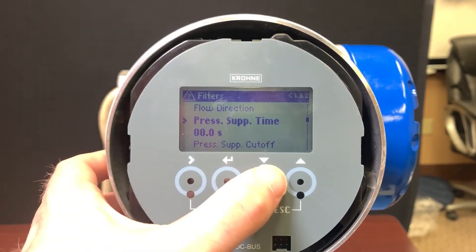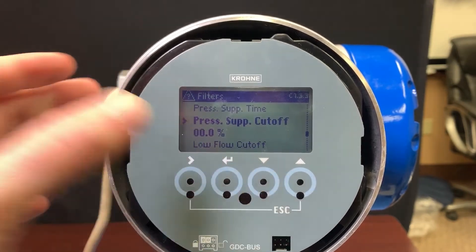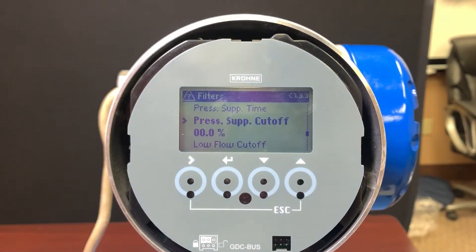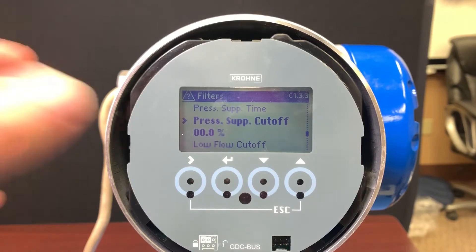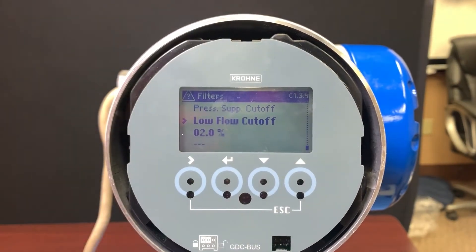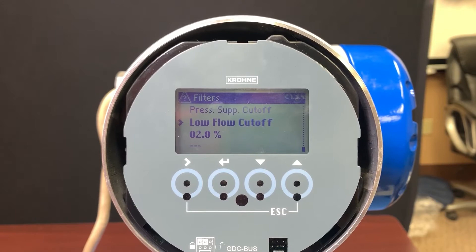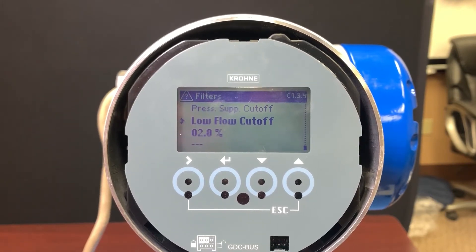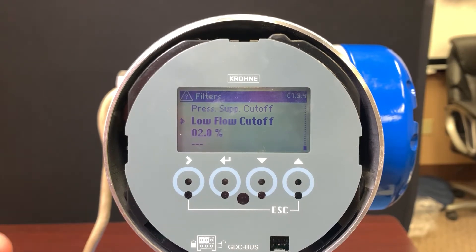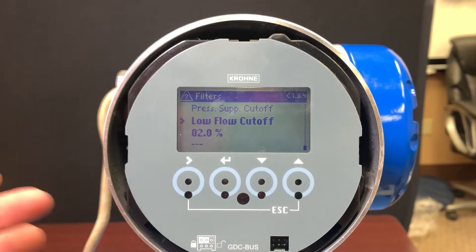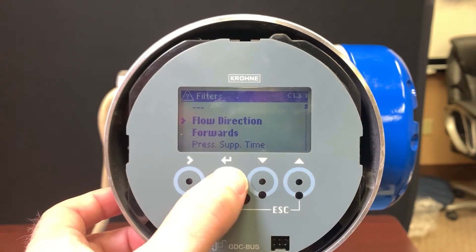Suppression time is something you're probably not going to see often, but it handles measurement impacts due to pressure changes. Low flow cutoff is one you may have to use quite regularly. This is used to buffer out instances of low movement where not only does our uncertainty potentially increase, but where other things might happen in the system that you don't want to measure. So low flow cutoff is one we use quite often.